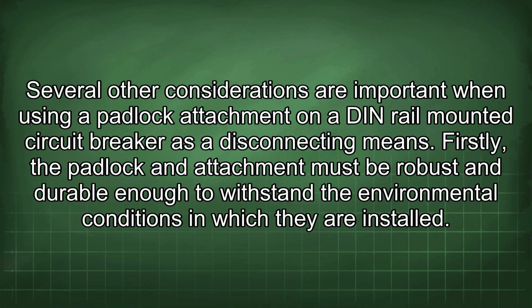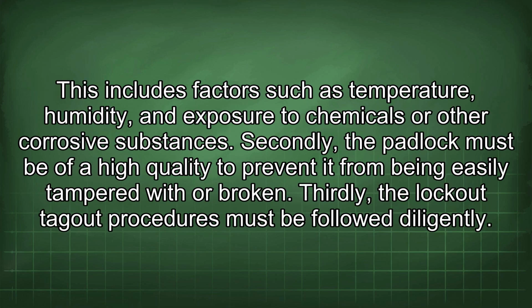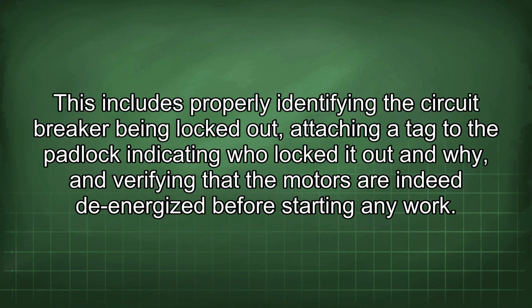Several other considerations are important when using a padlock attachment on a DIN rail-mounted circuit breaker as a disconnecting means. Firstly, the padlock and attachment must be robust and durable enough to withstand the environmental conditions in which they are installed. This includes factors such as temperature, humidity, and exposure to chemicals or other corrosive substances. Secondly, the padlock must be of high quality to prevent it from being easily tampered with or broken. Thirdly, lockout-tagout procedures must be followed diligently. This includes properly identifying the circuit breaker being locked out, attaching a tag to the padlock indicating who locked it out and why, and verifying that the motors are indeed de-energized before starting any work.